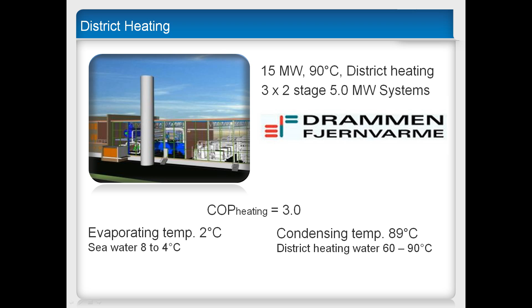The next project involved sucking water out of the fjord at 8 degrees and cooling it to 4 degrees in a town in Norway. We take roughly 10 megawatts of heat from there, add electricity to drive the system, and deliver 15 megawatts of heat, heating the district system from 60 to 90. In a UK context, for example, the Clyde has a capacity of heat that far exceeds the likely future heating requirements of the city, if we gather waste heat and use it.